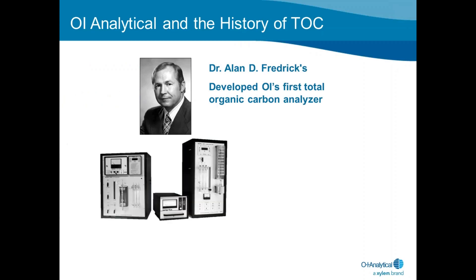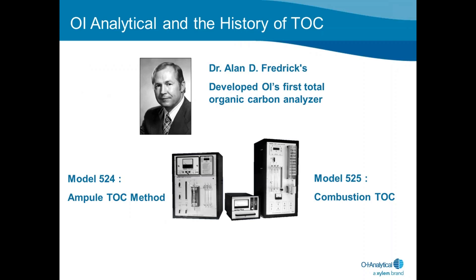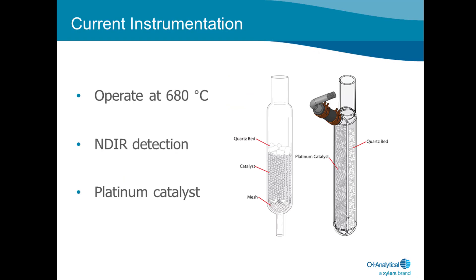As for OI Analytical's history with TOC, Dr. Alan Fredericks developed OI's first total organic carbon analyzer, the models 524 and 525 — you see on the right-hand side the combustion TOC. In current instrumentation today, systems operate at 680 degrees C and for the most part use NDIR as the detection technique, oxidizing samples over a platinum catalyst. The combustion tube design can be found in most high temperature catalytic oxidation systems on the market today, and by and large most combustion TOCs follow these basic criteria for determination of TOC.